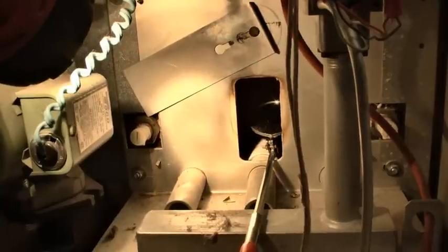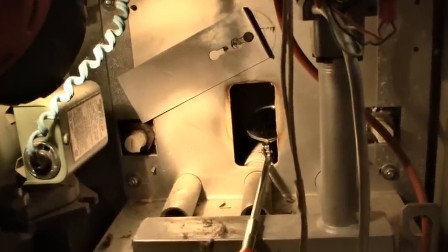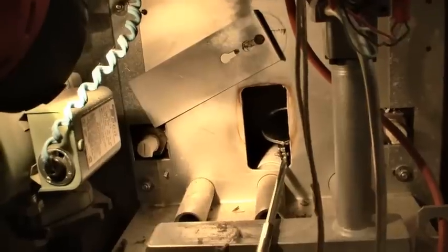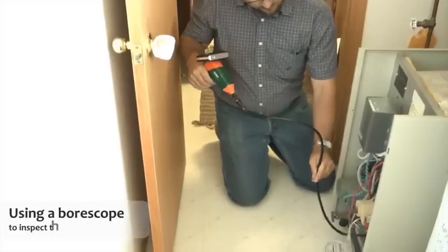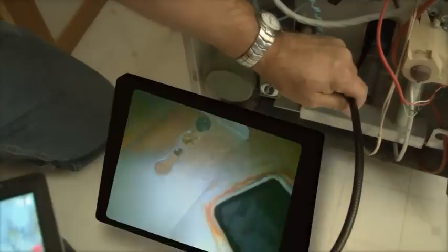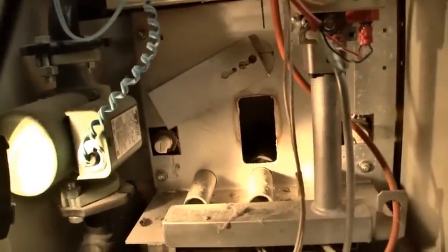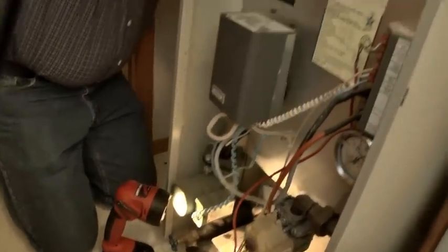And we can take our mirror here, and we can take our flashlight, and we can look up into the heat exchanger, and we can see whether or not the openings have carbon buildup or dirt or dust in that area. And if there is, then we need to clean that out. To clean that out, you have to use a brush. And a lot of times you'll move up to the top of the boiler. You'll pull out the bottom burners, and then you'll have to go to the top of the boiler.